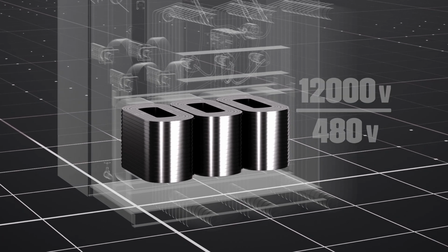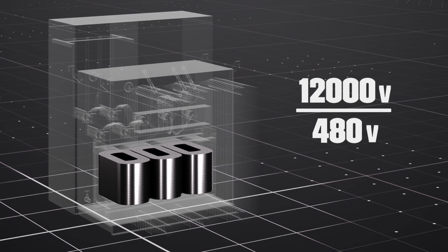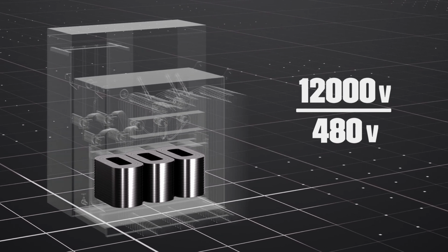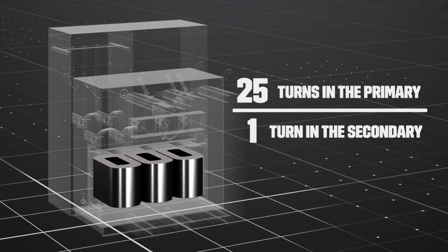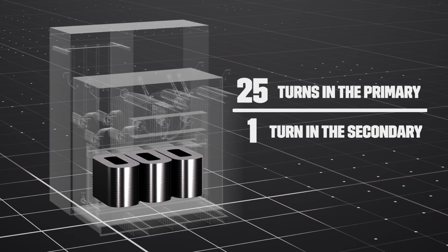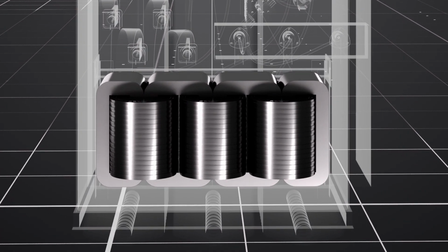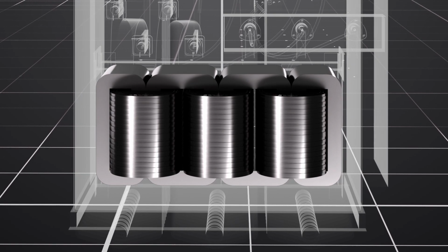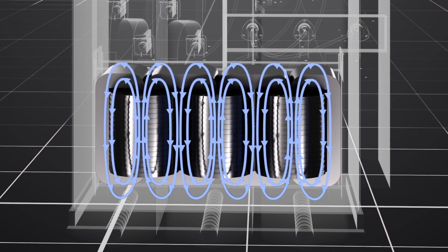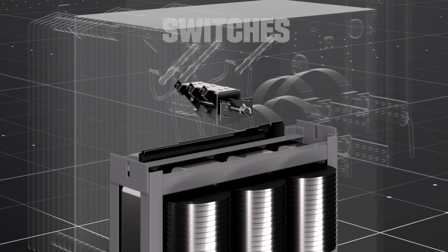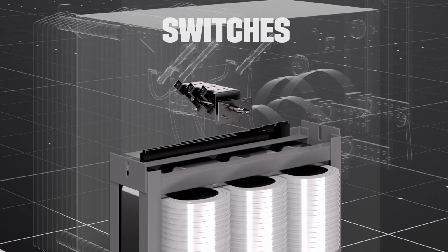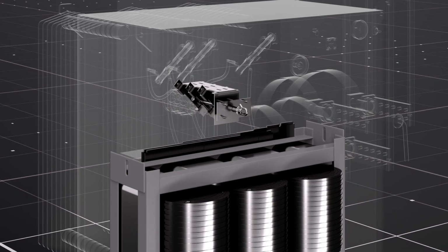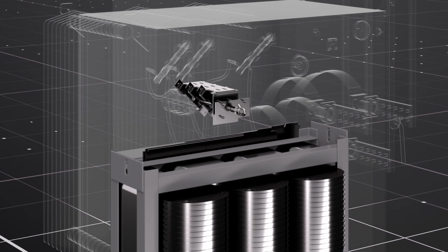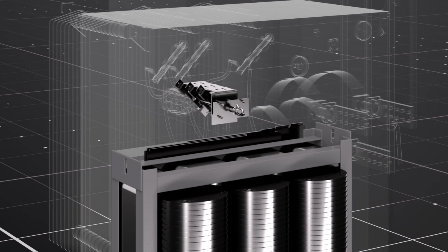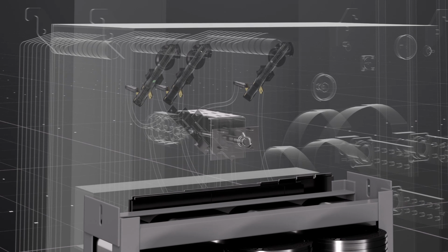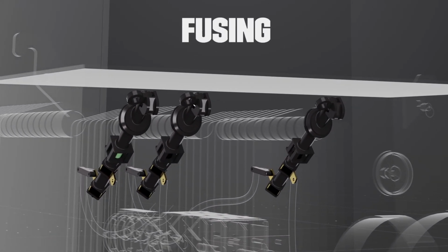In this example, our primary voltage is 12,000 volts, and our secondary voltage is 480 volts. That's a ratio of 25 to 1, meaning for every 25 loops in the primary coil, there's one loop in the secondary coil. The coils are looped around a special steel core, which picks up the magnetic field from the primary coils and strengthens it for better induction. A special rotary switch is used to manually disconnect the transformer from the power source as needed. These types of switches are called load break switches because they can function even when the transformer is energized and under load. Fuses protect the electrical system in the event of an overcurrent situation.